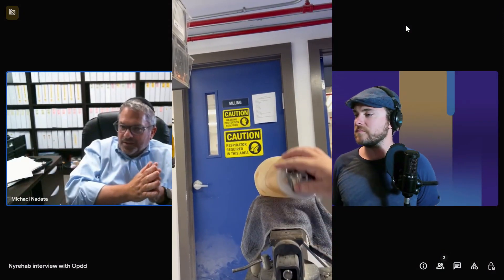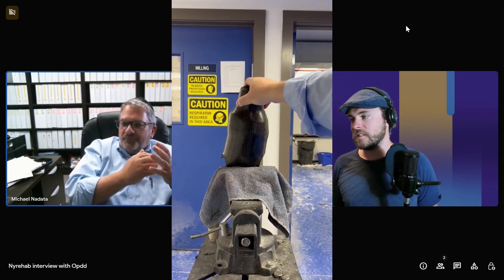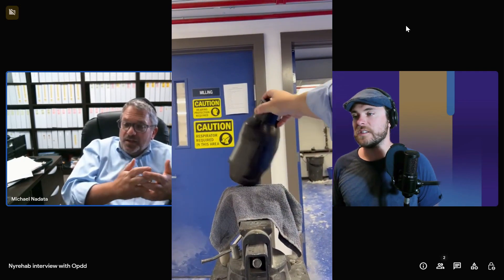I always used to give the example of a run-flat tire — the idea is that the run-flats would get you to safety. You could be driving down the road and you drive over a sturdy nail, you don't fly into the wall, you pull over. It gives you that time to drive the extra five miles to safety. And that was felt that a prosthesis — even carbon, even whatever — if there's a failure of the device, even if it fails, it shouldn't be a catastrophic failure. It should support the person enough so they realize something is wrong: I need to sit down and I need to have a service. That was always the minimum I was trying to achieve. And when something would just shatter, that wasn't a minimum. That was just not good.